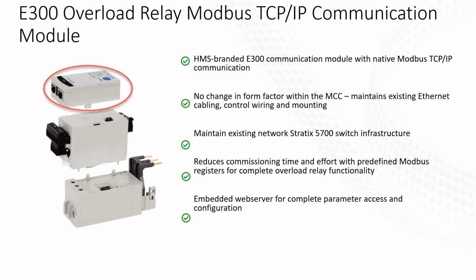We'll not have a Rockwell part number, but I want to make sure everyone knows this exists, because this is a situation we run into a lot of times. We have an older system where the protocol they're using is Modbus TCP. This gives us an ability to make direct connections without having to put one of our controllers in there to act as a gateway. So it can simplify a lot of our motor control center business.